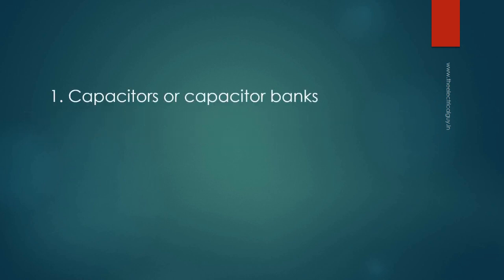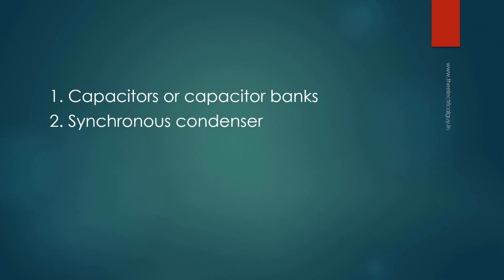The three methods are: 1. Capacitors or capacitor banks, 2. Synchronous condenser, 3. Phase advancer. The reactive power generated by these three methods is capacitive in nature, as most of the time the load is inductive — like transformers, induction motors, and so on.